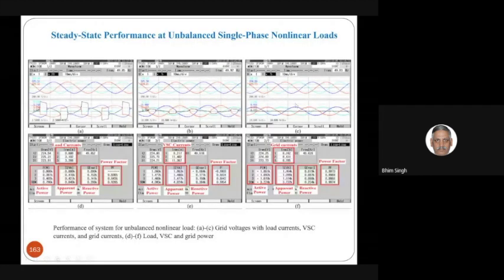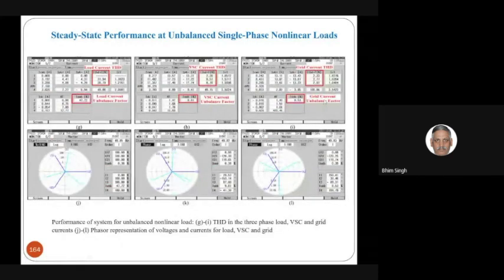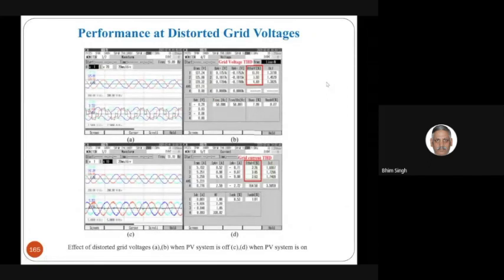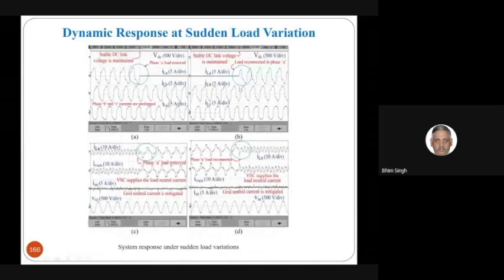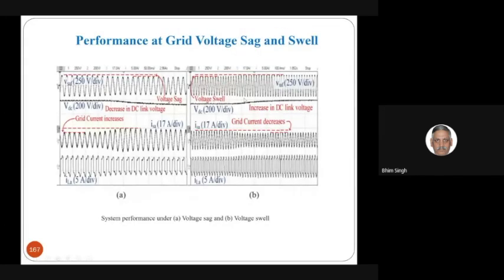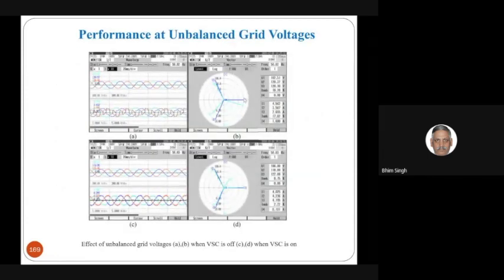This is the performance of the grid current, and you get the converter current, the load current, and the grid current, which are balanced and sinusoidal. And these are the THDs: the load current THD is 31%, then you have the grid current and VSC current here, and the grid current THD is even less than 3%. Then the performance under sudden grid voltage change works very well without much fault. And the load removal and load application, how the performance is affected. And the performance under unbalanced voltage: there you have unbalanced voltage, but you have a balanced voltage in the signal, and then you have balanced grid current.